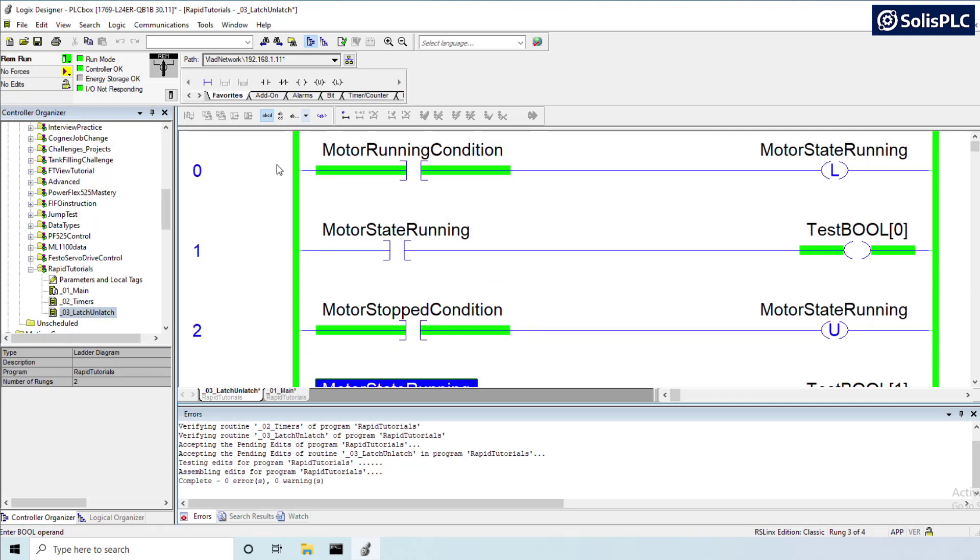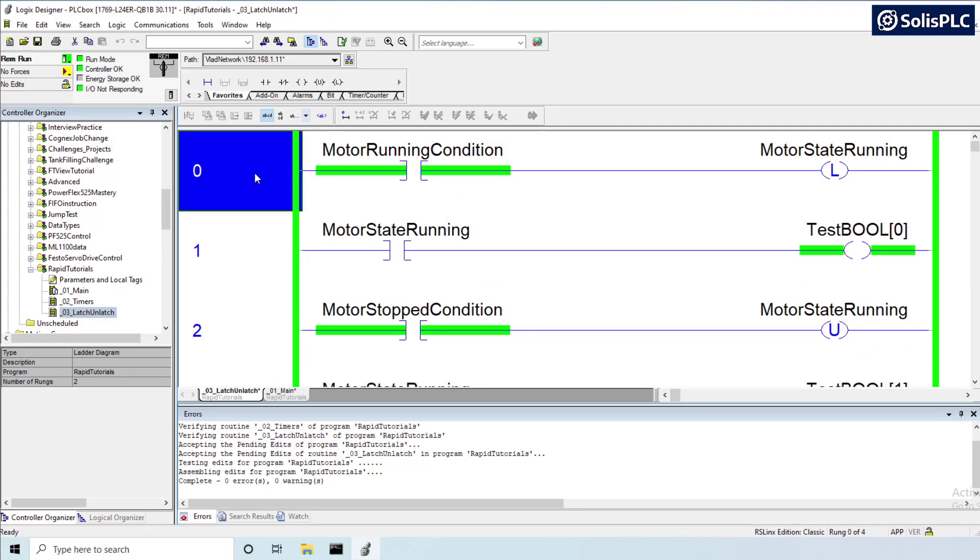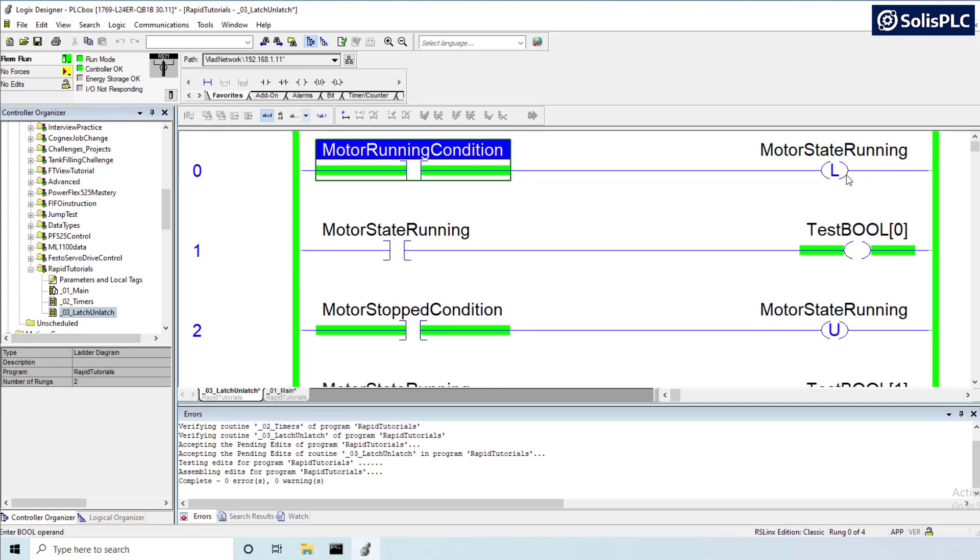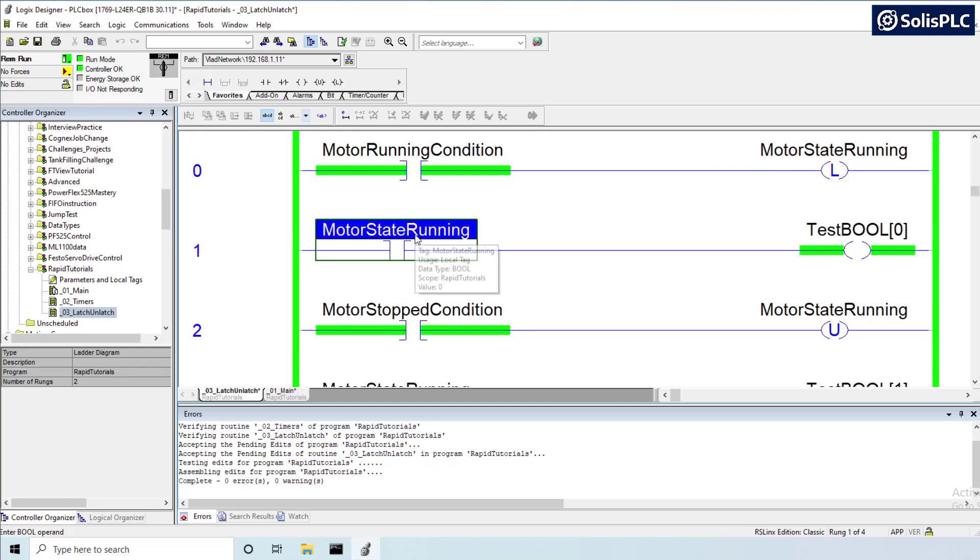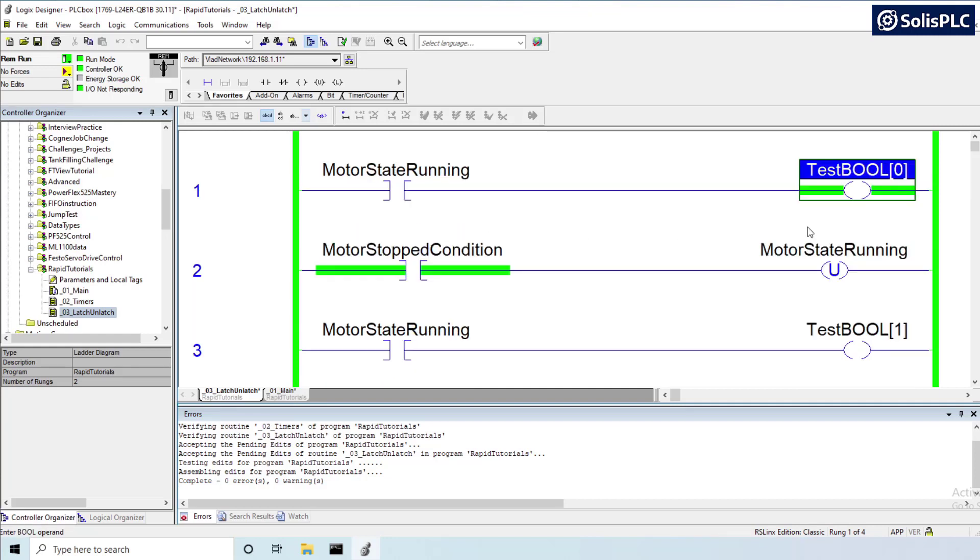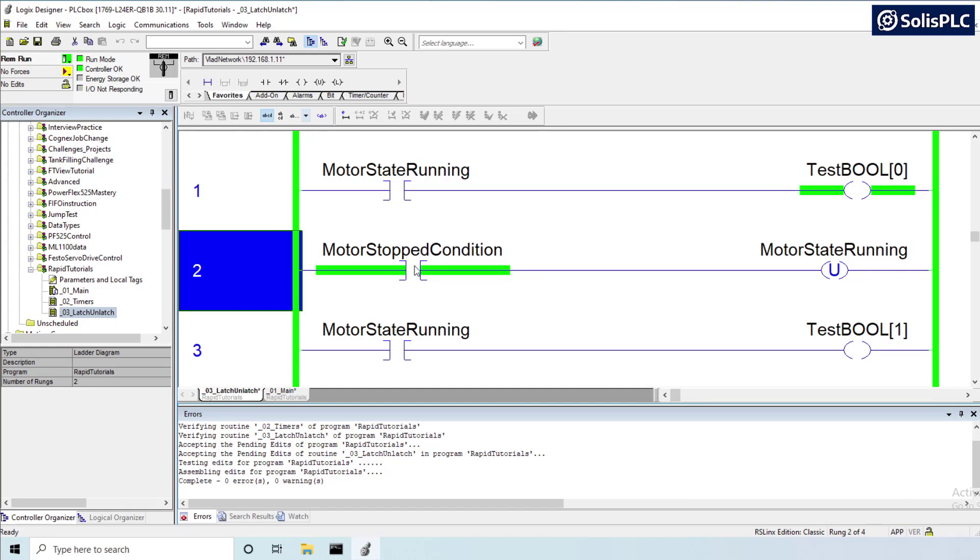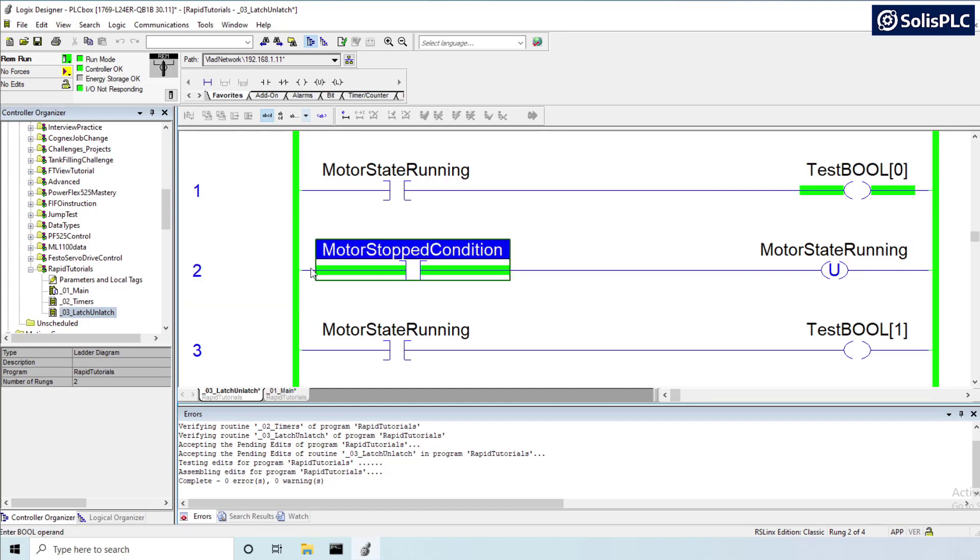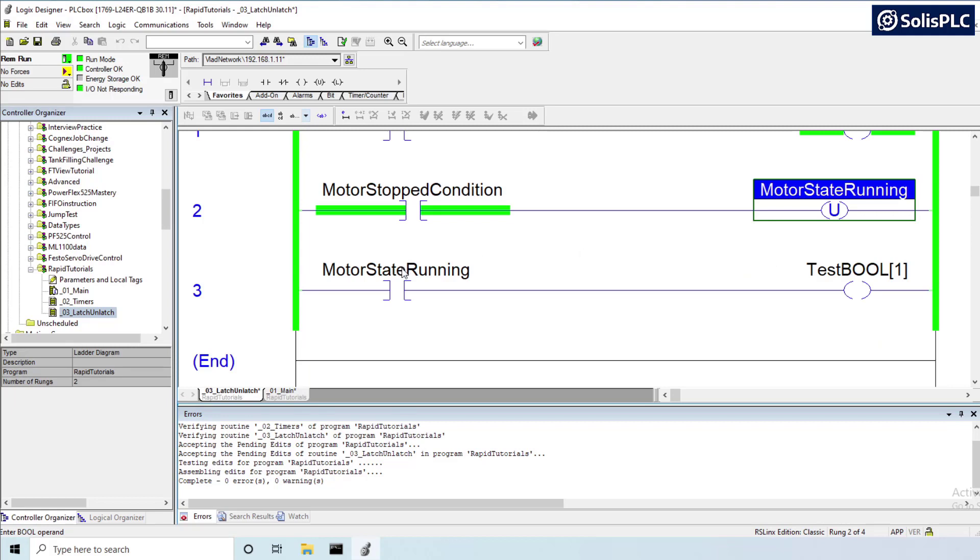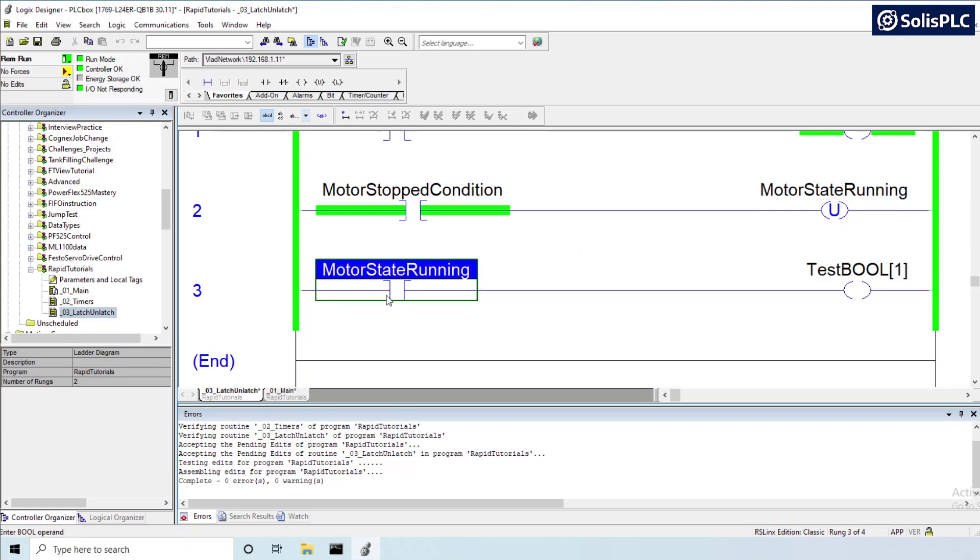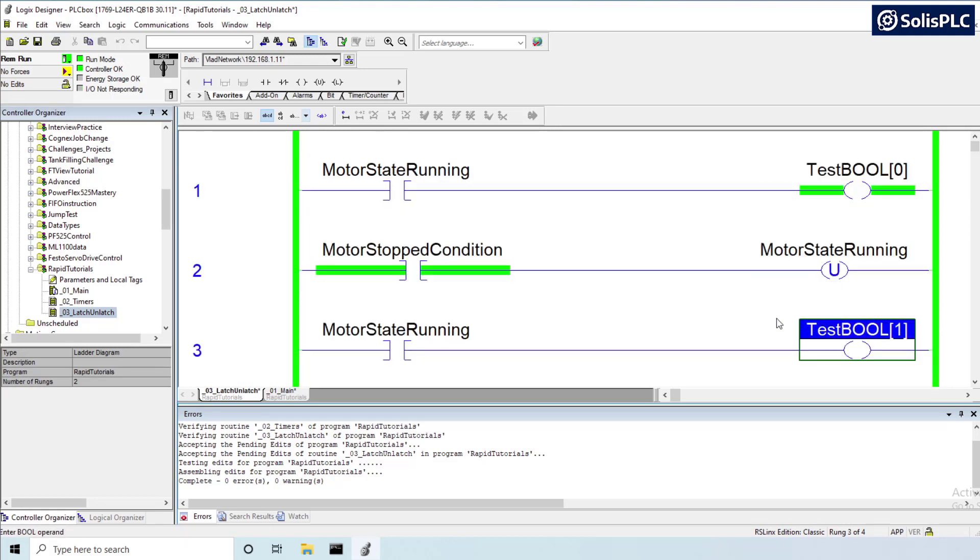Let's examine the logic first and foremost and so the first thing that we need to realize is that a PLC reads logic in a sequential manner. So rung zero is being executed, we are latching this motor state running so it is high as of rung zero. As of rung one it's also high, it is currently one, so once we're testing this XIC it is setting this test boolean zero. Next we are giving this a stop condition so we're de-energizing motor state running and therefore in rung three it's not setting this test boolean one.